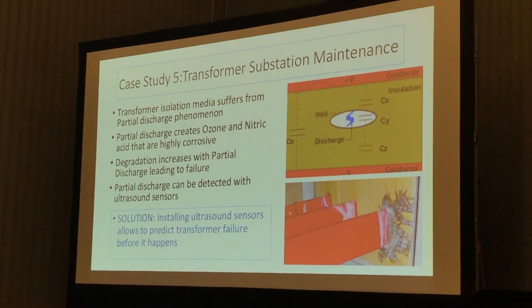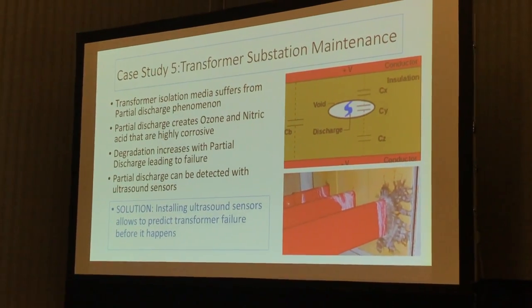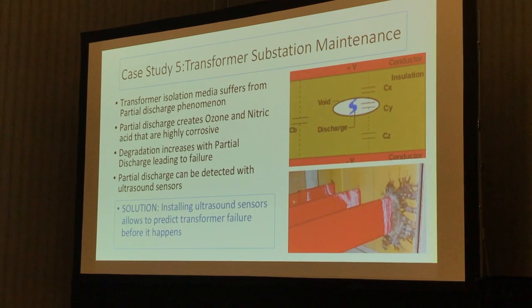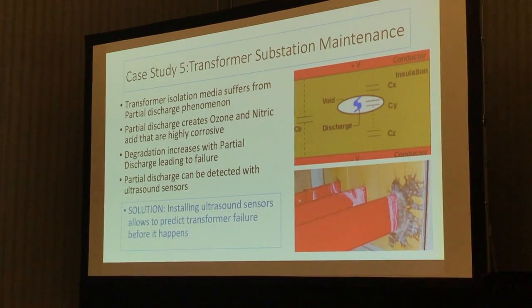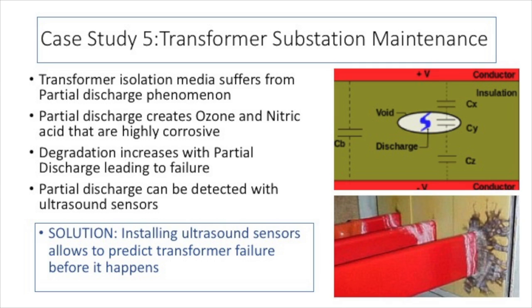So here's case study number 5, transformer substation predictive maintenance. We started this project as requested by several utility companies. The target here was to design a predictive maintenance system that works with electrical distribution transformer substations, with a special focus on assessing the real condition of the transformer by measuring the partial discharge phenomenon.